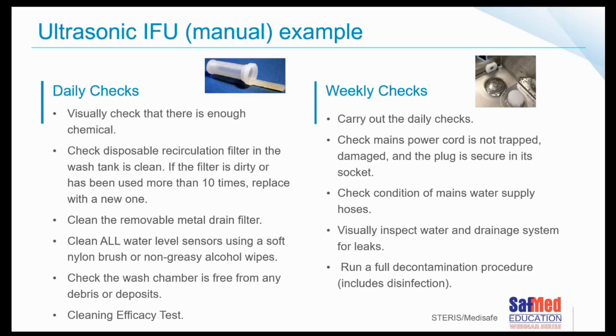Visually check that there's enough chemicals. Of course, that would be your detergent. Check that the device or the pump that's meant to go into the bottle to suck up the detergent fits in correctly, and it's properly inserted into the detergent, not only three-quarters of the way up, or you might end up sucking air at the end of the day. If there are disposable recirculation filters in the tank, check them. If they need to be replaced, you do it as per the manufacturer's instructions for use. There may be a metal drain filter. If there is one, how often are you meant to clean it? What are you checking for?